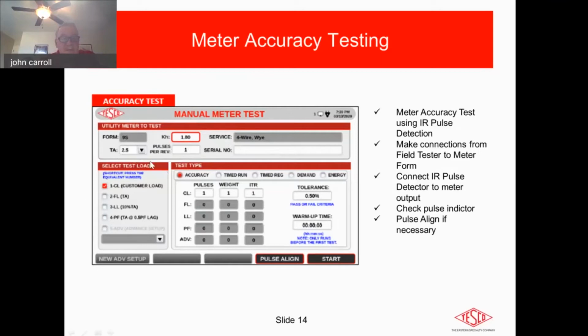On the left-hand side here, you can see the test loads under what we're going to actually select. In this case, we're going to do just a customer load that we mentioned before, although I will use this same screen a little later on to show you the full load, light load, and power factor. There are different test types you can run. The majority of the time it would be accuracy, but there are timed runs sometimes. There are timed registrations, maybe a 5-minute demand or 15-minute demand test could be required. These are all options that you have when you do your procedural testing.